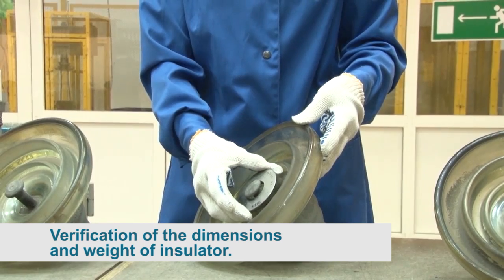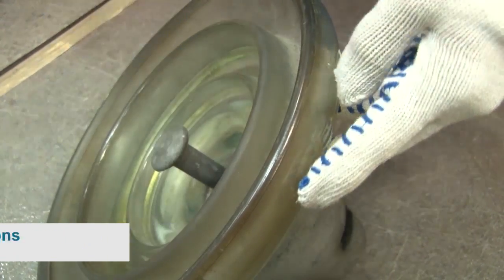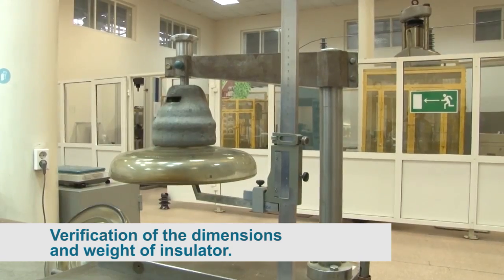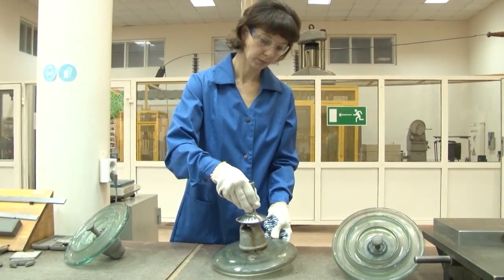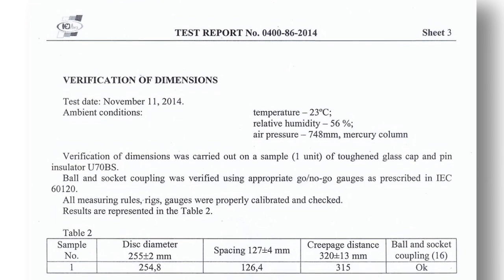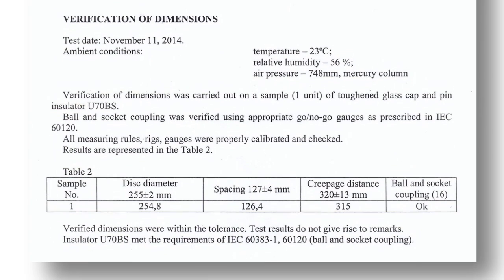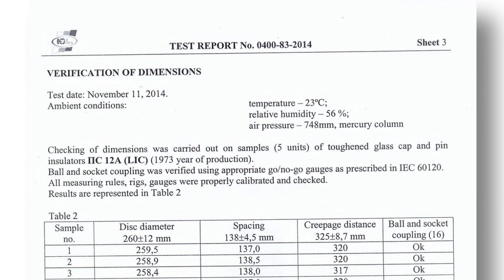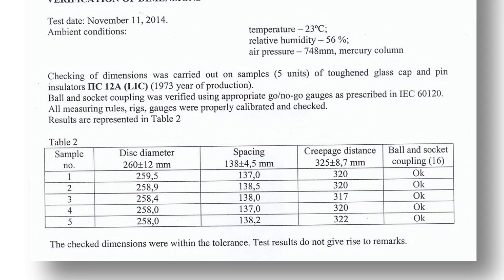25 insulators were chosen for tests, and 12 different tests were performed for each type of insulator. Verification of dimensions and weight of insulator type PS-12A showed a creepage distance range of 317 to 322 mm. For insulator type U70BS, the creepage distance is 315 mm, within acceptable standards. Both types meet the IEC requirements.